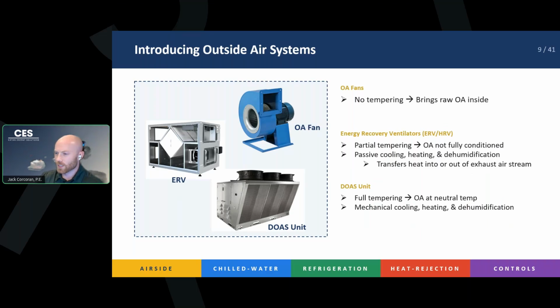So what type of outside air systems can we actually go with, right? Are we going to just bring it in with an outside air fan? Maybe we'll use an ERV to slightly temper the air, or maybe we need a full-on DOAS unit that uses mechanical heating and cooling. These are, I guess, a simplified version of the types of systems you can use. There's quite a wide variety, but essentially, this is your low, medium, and high levels of tempering your air before it reaches your space. If you start at the top here, our outside air fans, there's no coil in this, right? It just brings the raw outside air into your space. And as we said, maybe that's not ideal on your hottest days in the summer or on your coldest days in the winter because it carries a significant heat load with it.